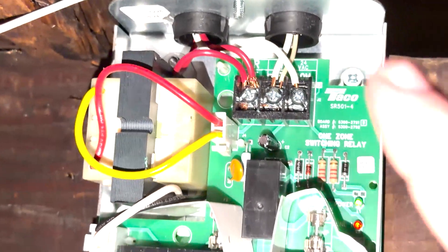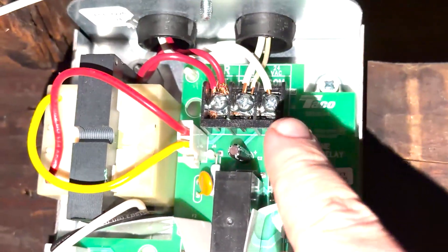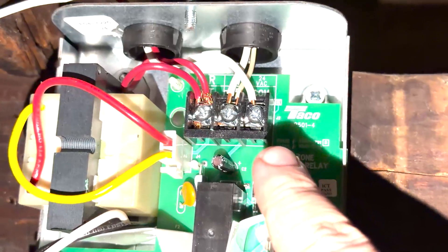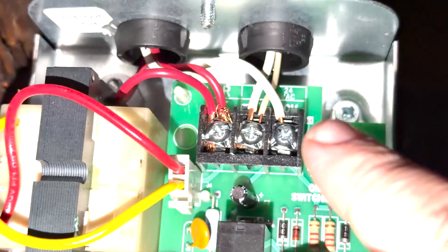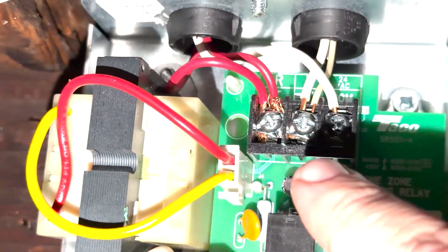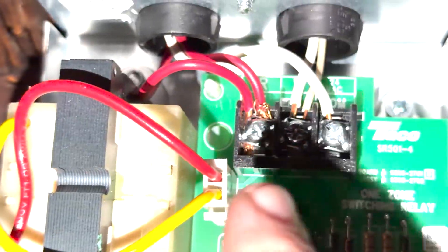Basically, you're going to take the white lead off the common port of the transformer, which is here, this white one, and you're going to connect it to this terminal here. Then you're going to take the red wire and you're going to connect it to red.